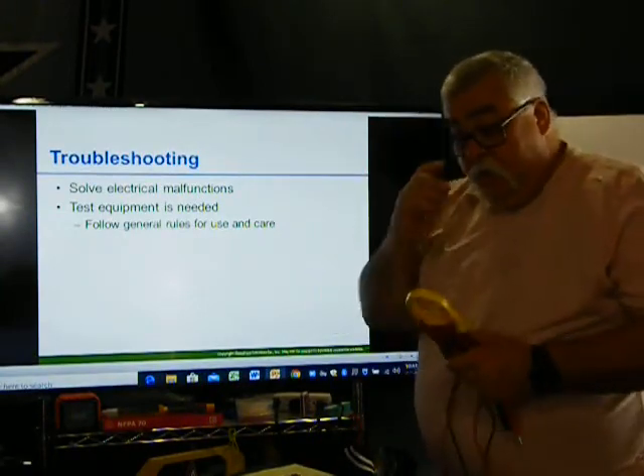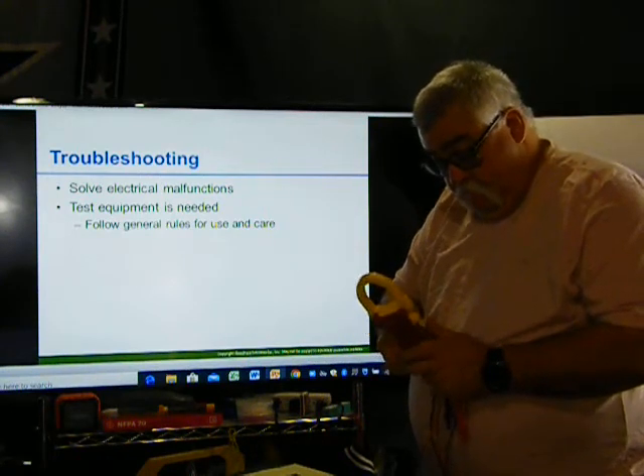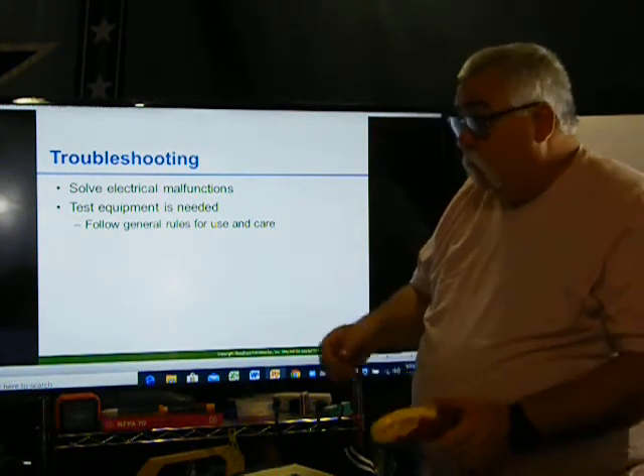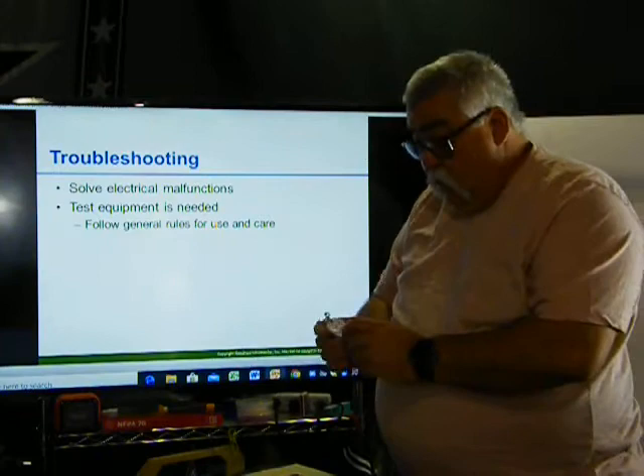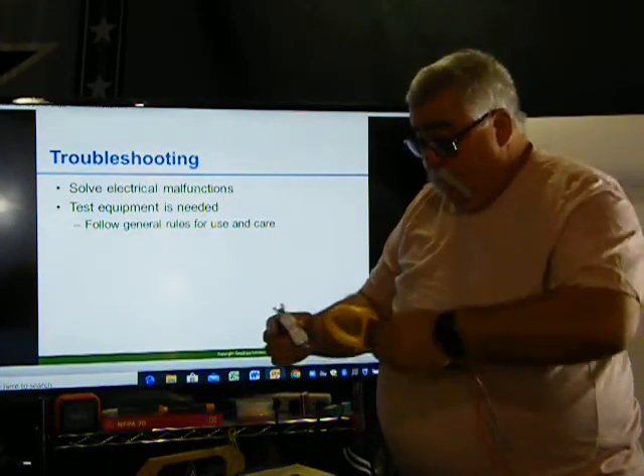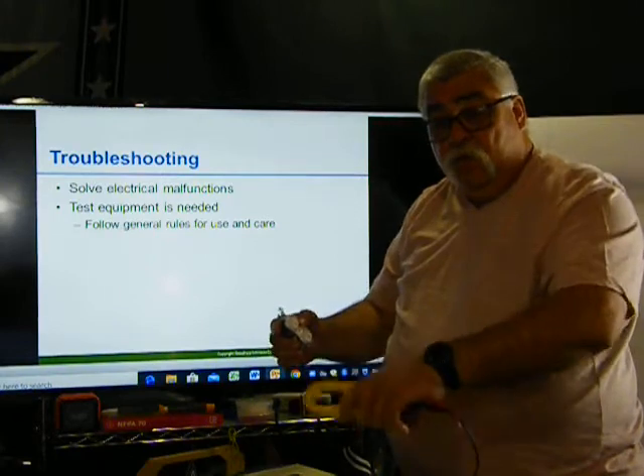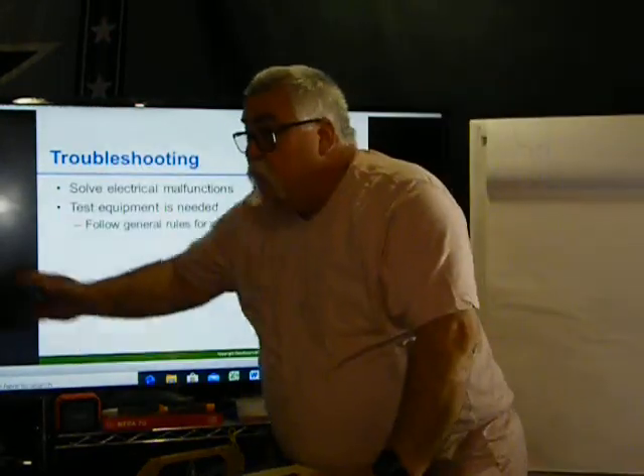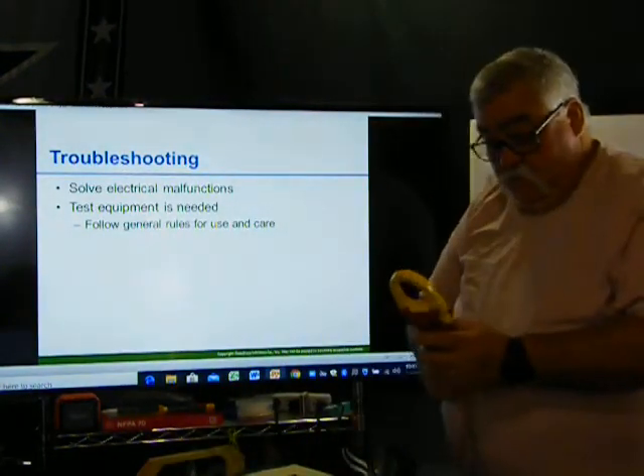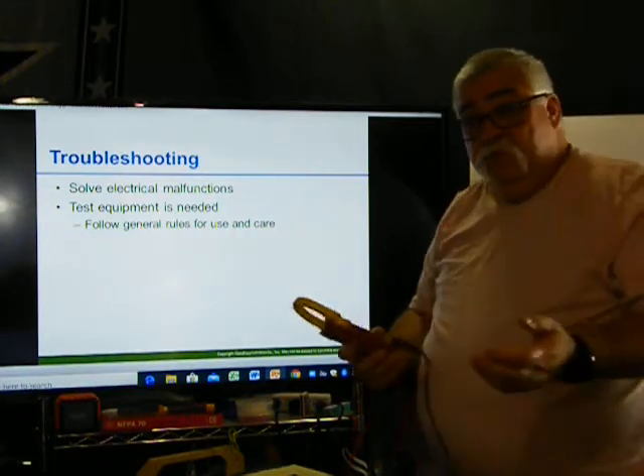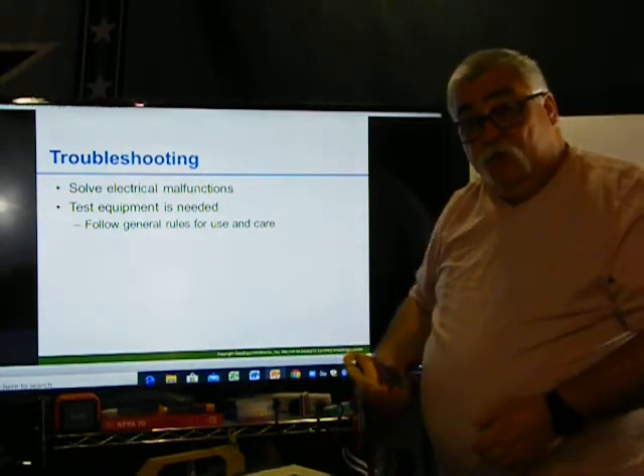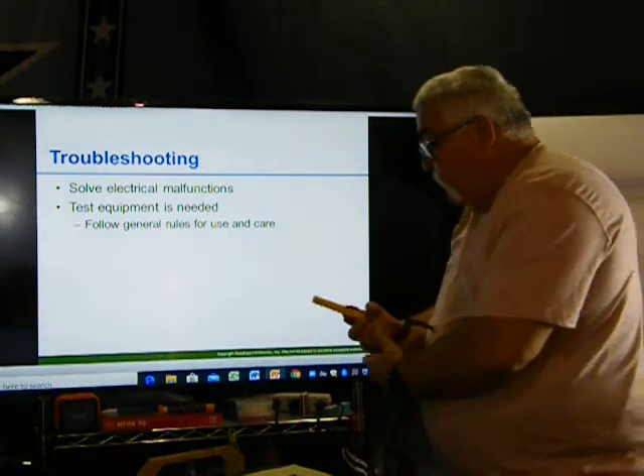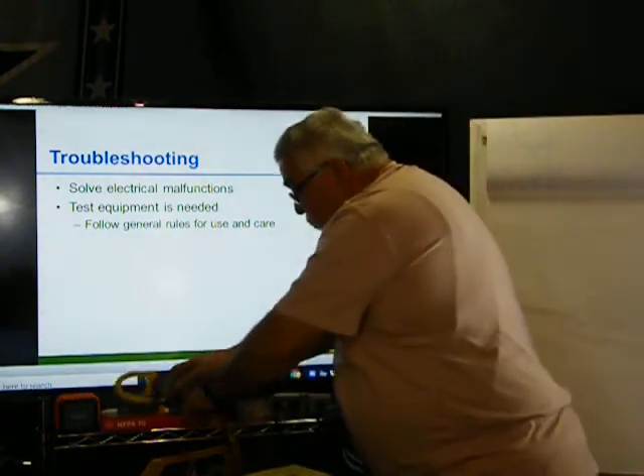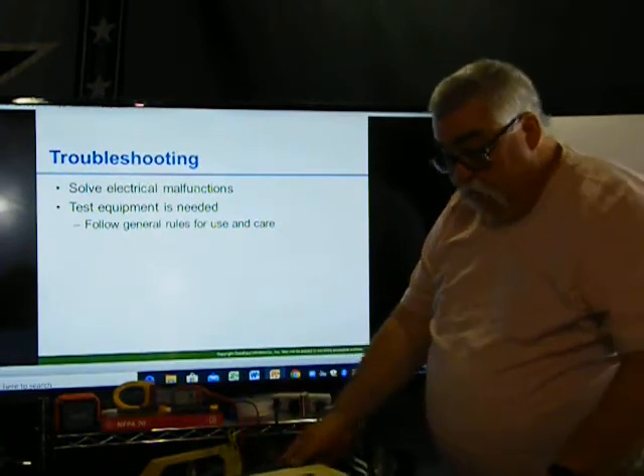They do make a plug-in one that you can plug into an outlet. I don't have it. Never used one. But you plug it into the outlet and you just clamp it. Now you can read amperage going across that outlet. It's a good little thing. I've never needed it. So yeah. And if I had to measure amperage, I pulled the receptacle out and clamped around the wire, around the hots, and found amperage that way. Or go back to the panel and read the amperage of the circuit.